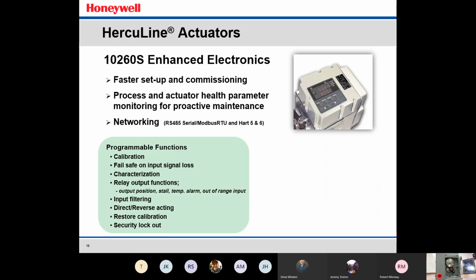The enhanced version offers faster setup and commissioning of the actuator, so you can basically stock one model on the shelf as a spare and pre-program it so that in the event that there is a failure out in the plant, you can take it off the shelf, go out, set up the linkage, put it in process, and be up and running in a very quick manner.